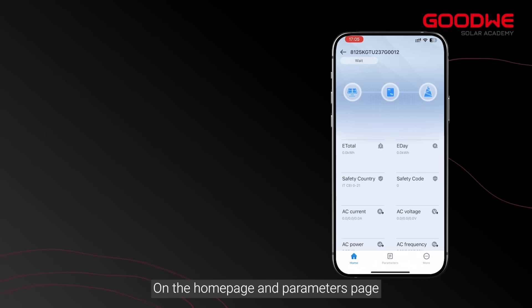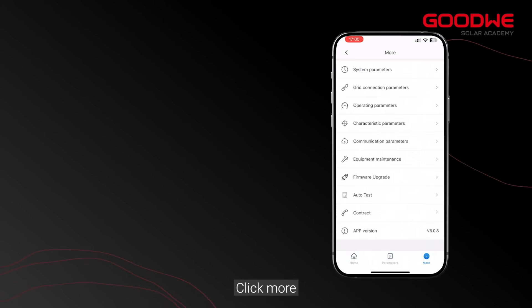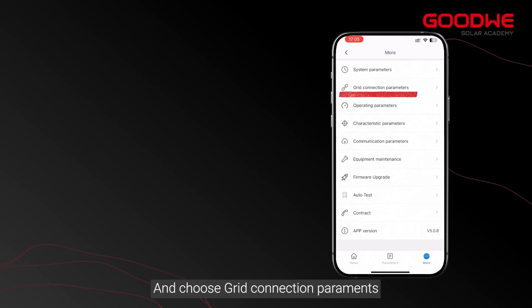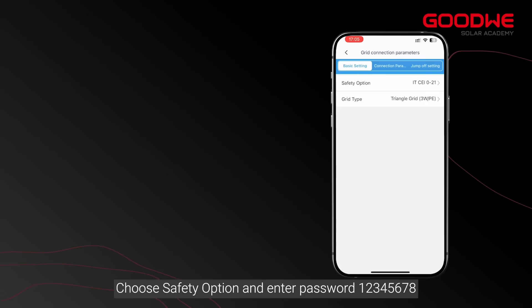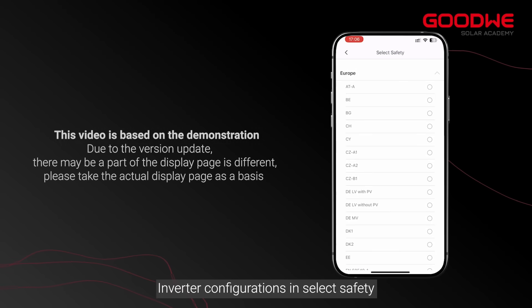On the home page and parameters page you will find basic data about the inverter. Click 'More' and choose 'Grid Connection Parameters'. Choose 'Safety' option and enter password 12345678 for inverter configurations to select safety settings.